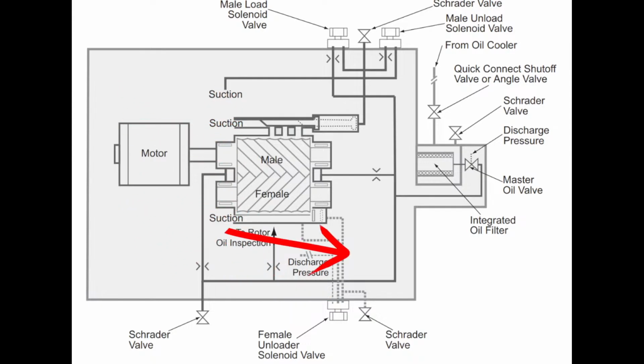Okay, so by the way, this picture is in the RTAA IOM manual. If you ever want to pull this up, read about this compressor deeper and get into it a little bit further, that's where I would suggest you can go, and it actually does a pretty good job explaining a lot of this and breaking it down. But the female unloader specifically is down here, and it is different from the male load and unload solenoids and valves. These up here are what are controlling the slide valve, and that was the second part of the question. We'll get to that. But the first part is primarily focused on the female unloader.